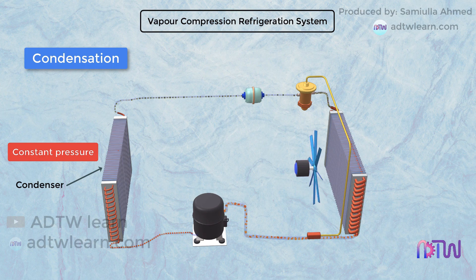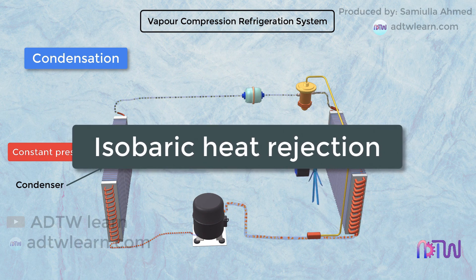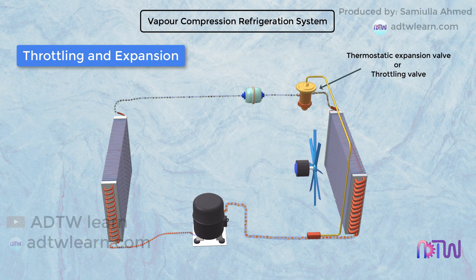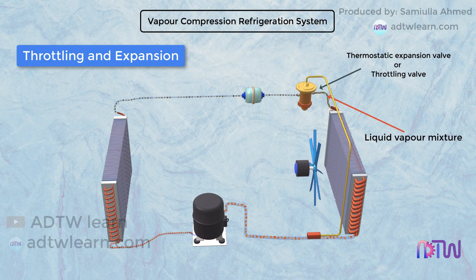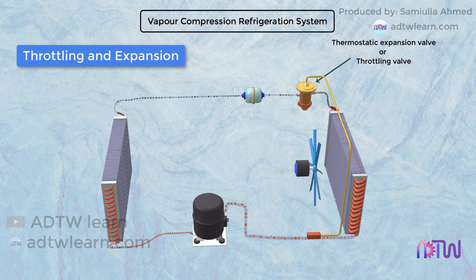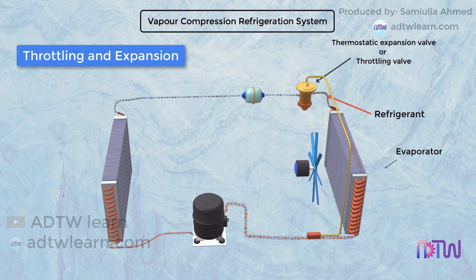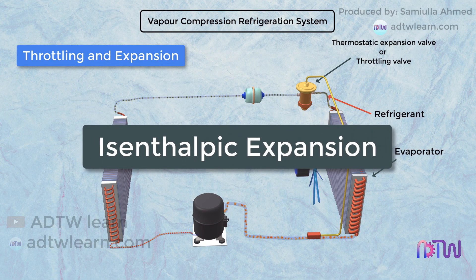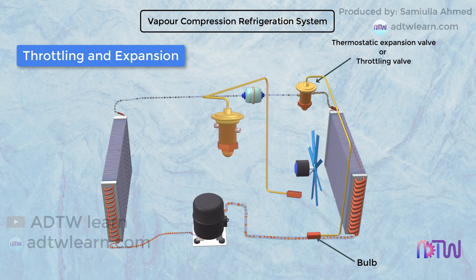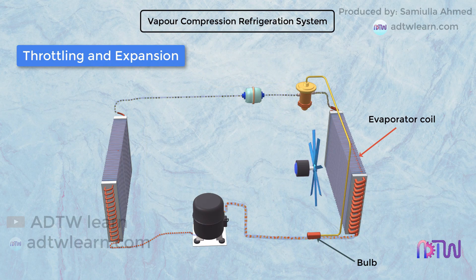The refrigerant flowing through the condenser is at constant pressure; therefore, we call this process isobaric heat rejection. When the refrigerant enters the throttling valve, it expands and its pressure reduces. As a result, the temperature drops, and the refrigerant leaves the throttling valve as a liquid-vapor mixture. The throttling valve plays two essential roles: first, it maintains a pressure difference between the low and high pressure sides; second, it controls the amount of liquid refrigerant entering the evaporator. This step is called isenthalpic expansion. Normally, a thermostatic expansion valve is used, with a bulb that senses the temperature of the refrigerant coming out from the evaporator coil, adjusting the amount of refrigerant passing through the expansion device.